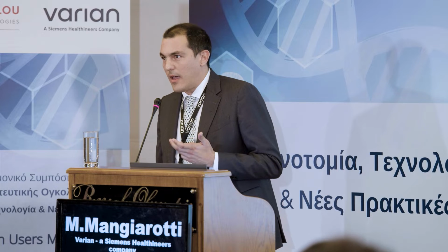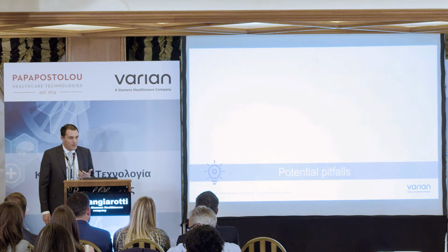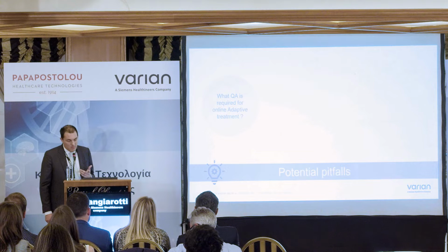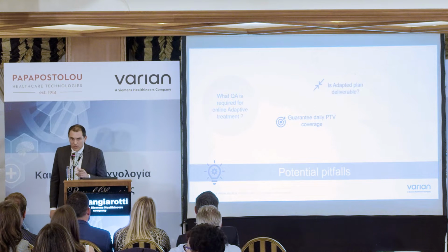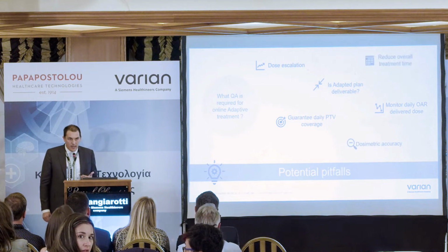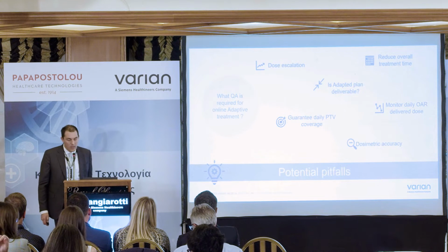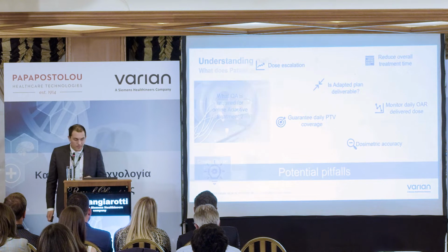So a question may arise here, is QA still needed? Well, as a medical physicist, I would say yes, because there are still a lot of potential pitfalls involved. We still need to check the deliverability of the plan. We still need to check if the dose is going where it should go, if the PTV is covered, if the organs at risk are spared, and so on. So we still need to QA.